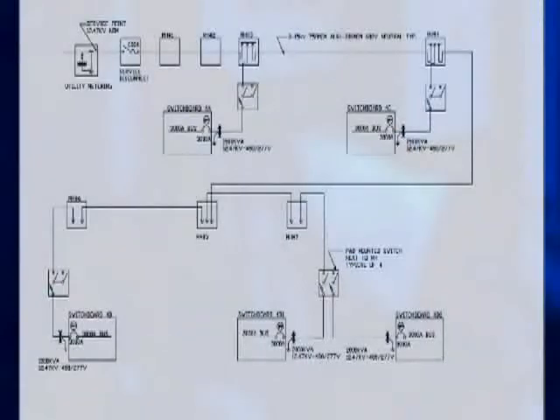So, if you suspect an unbalance issue, go downstream to the next load and check phasors until you find the source of the problem. The most common cause of unbalance is a change in load configuration. It may help to quickly map out your overall equipment distribution system and develop or update your load schedule and drawings. Total the loads per phase and verify each phase carries a fairly equal load.